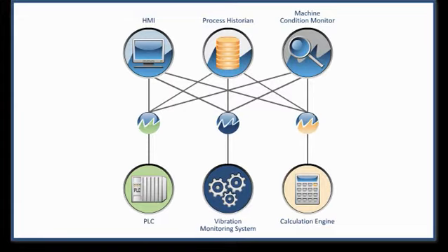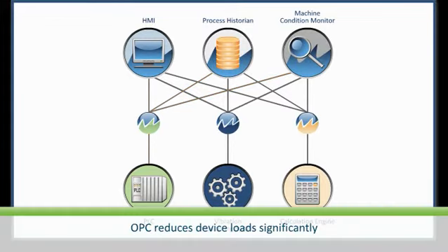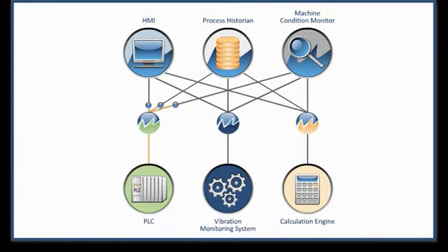When an OPC server received 3 data read requests for the same point, it only had to send a single request to its data source. This drastically reduced the data request loads on each data source to 1/3 of the proprietary method, and significantly increased the performance for a slow serial protocol such as Modbus.